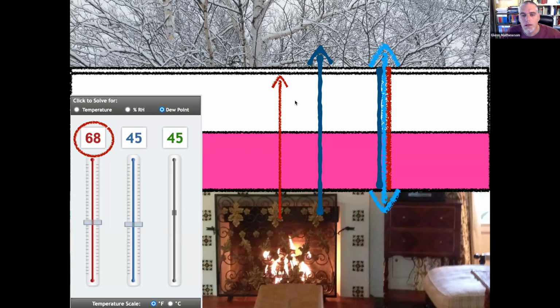But that also means that air temperature is what was keeping the dew point, the surface where we're going to get condensation occurring. That was the only source of heat for that surface. So while we do reduce air temperature, we're also reducing that 45 degrees, right? That dew point temperature is going to come down. It'll take a colder surface to condense to liquid water, if our air is colder. But if our air is colder, it's also going to lower the temperature of that surface. And so it will still continue to lower it. And what was happening? It lowers that down enough that now they're seeing condensation start to occur, because we affected the temperature only, again, focused on our comfort.